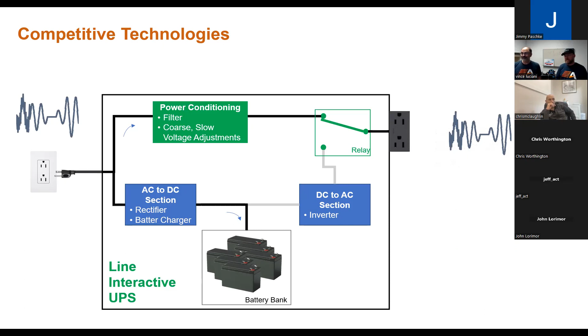It's not anything worth the amount of money you're paying for it, because 99.9% of the time it's going to be in this mode of operation. It's just not a good value in my opinion. The biggest part about it is, if you've got crummy power coming in, that crummy power is going to be just passed to the output during normal operation. That's just the misnomer on that.